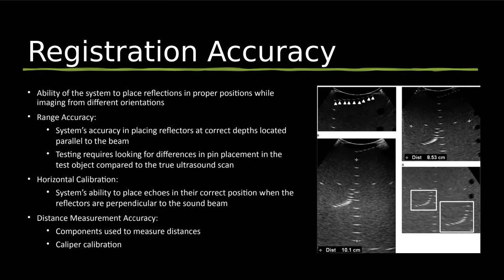And similar to those pins that we just discussed for the dead zone, we do so with registration accuracy as well. We're using all of these different pins and placements of pins to see how well the system can evaluate them. The physicist knows where these pins are placed in the phantom, and then they align that with how well the system can represent that. So if they know that this curve of pins appears at 5 centimeters depth, and our system is showing that as appearing at 7 centimeters of depth, we know something is wrong with that system and it needs to be recalibrated.